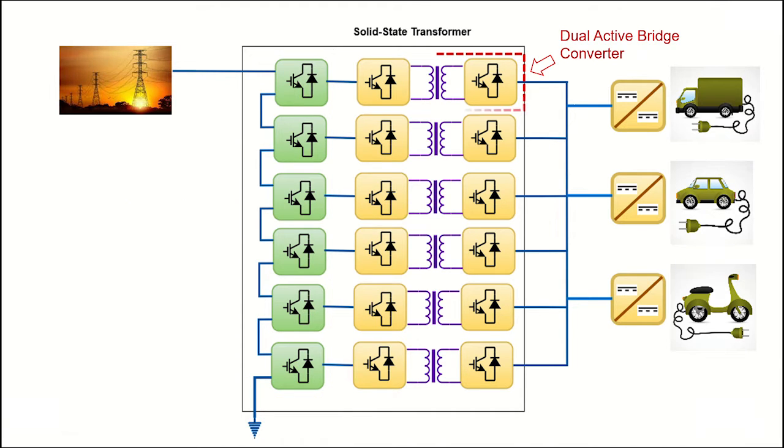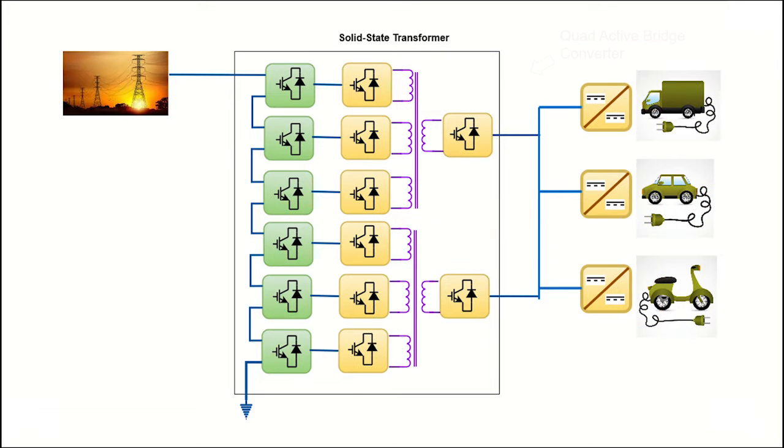Then, the dual-active bridges are connected to each sub-module of cascaded H-bridge. Here, several high-frequency transformers are used. I am proposing to use a quad-active bridge instead of several DABs so that the size and the number of converters can be further reduced.